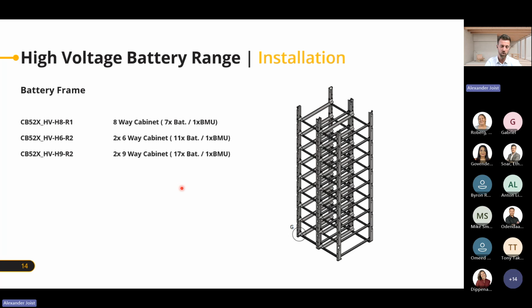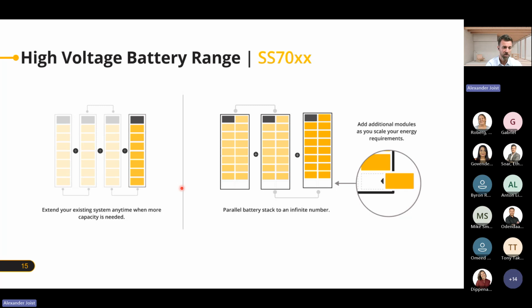So these are the single components of a high voltage battery system. If we build those systems, we can parallel them, of course. We have the possibility to have a single rack and then multiple single racks. It's important that we have the same amount of batteries in each, as well as with the double stack or double row batteries, also with multiples. And if they're not fully filled up, you can later extend them and add more batteries. If you have a multiple stack battery and want to extend it, you need to add, for instance on the picture here, 3 batteries - 1 per rack. So it's very important that you always have the same amount of batteries.